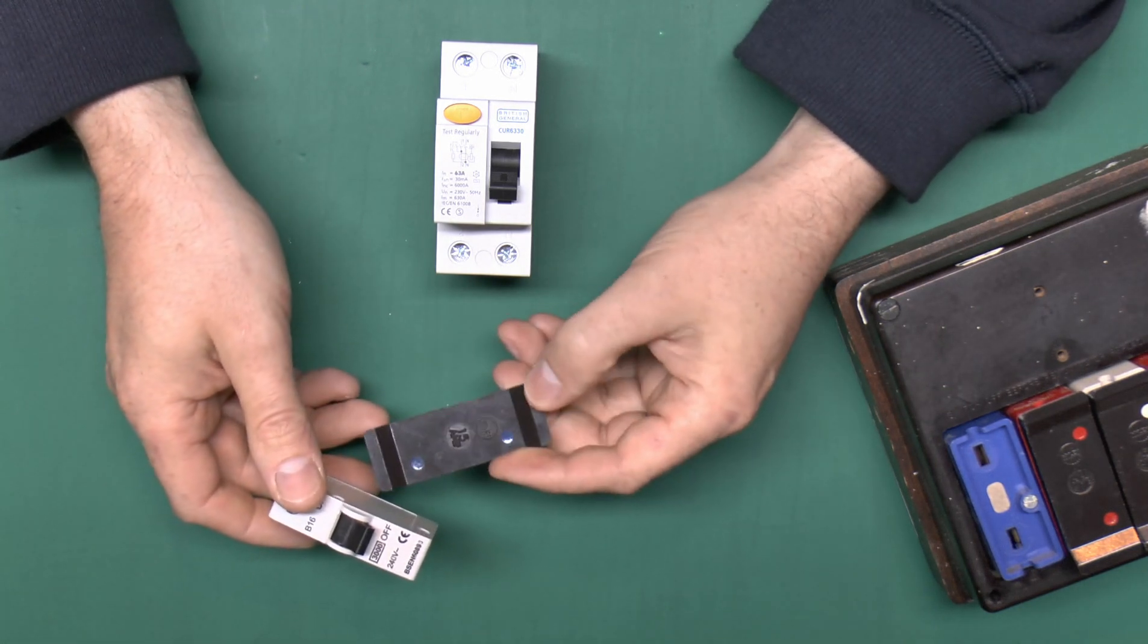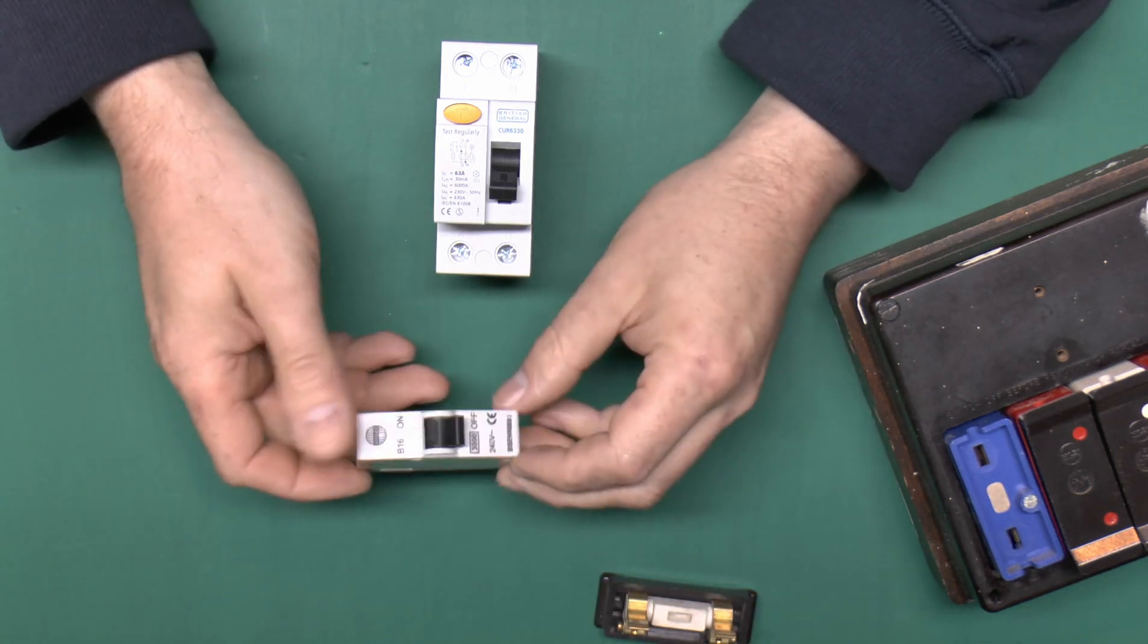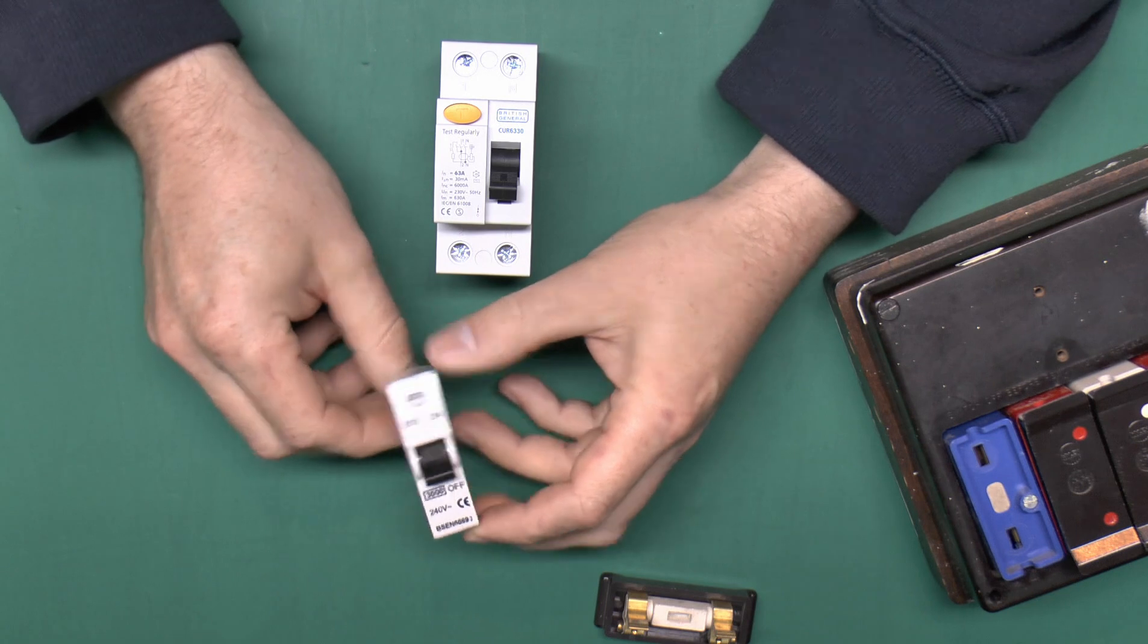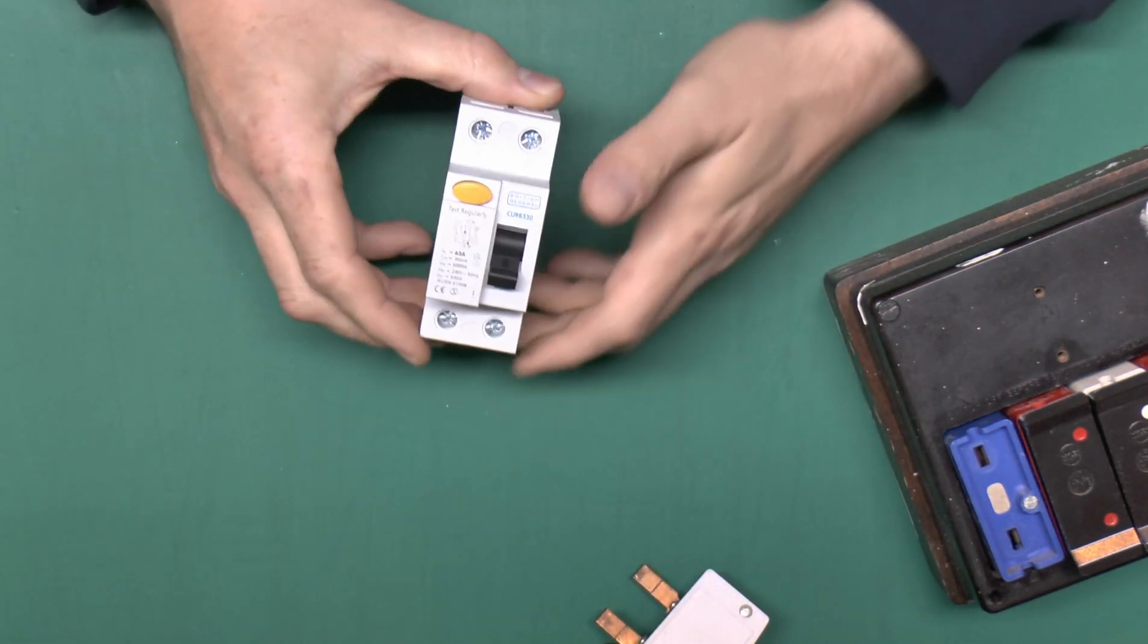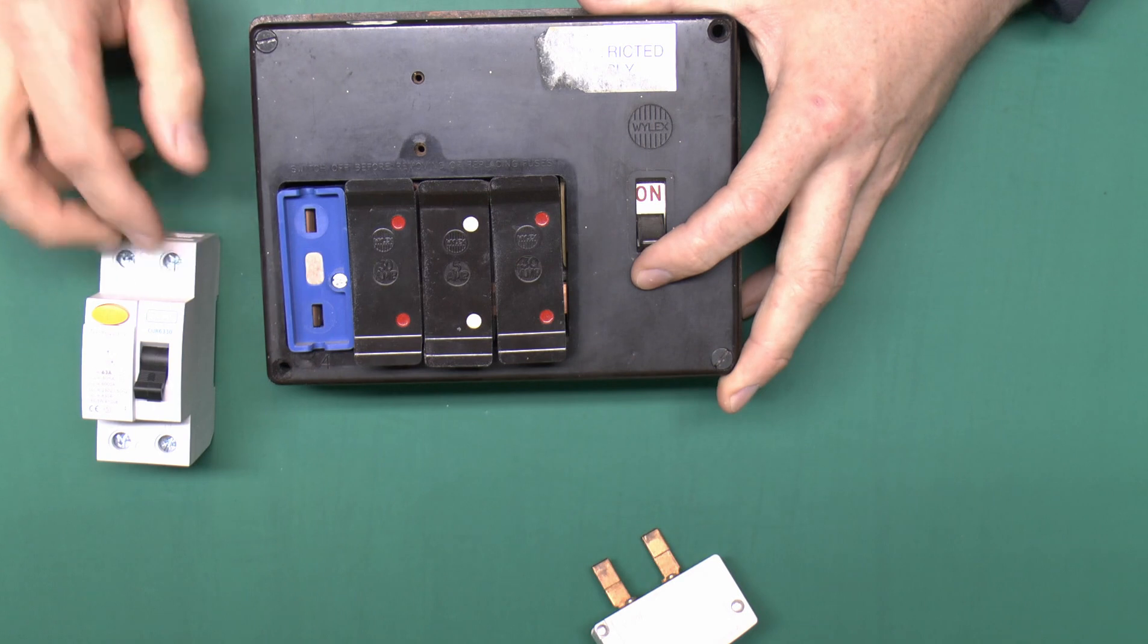This 15 amp fuse will allow well over 15 amps to flow for a very substantial amount of time. This thing here which is a 16 amp does the same thing. You could load this up to 16 amps and leave it there. It would just run all day long. So there's no way of fitting the equivalent of these into this box. These require a two pole connection. This is just a single pole.